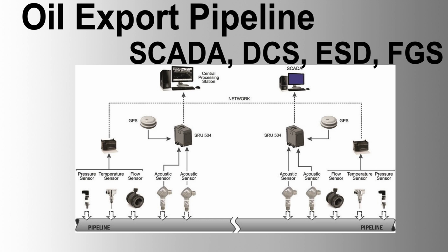Functional capabilities: data acquisition, real-time data collection from field devices and instruments. Visualization: graphical displays, trends, and reports for operator monitoring and control. Control: remote and local control of process parameters, equipment start-stop, and set point adjustments. Alarm management: real-time and historical alarms with acknowledgement, logging, and reporting features. Redundancy: hot standby configuration for servers and communication links to ensure high availability.